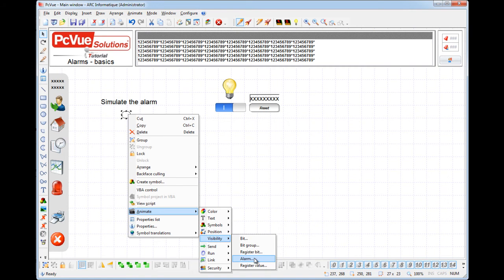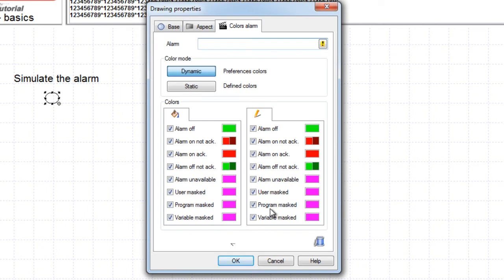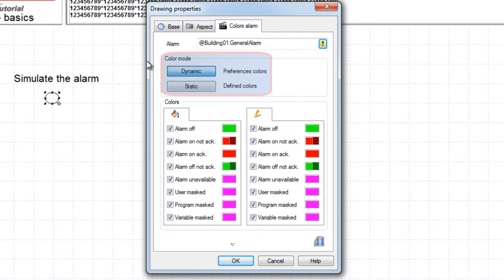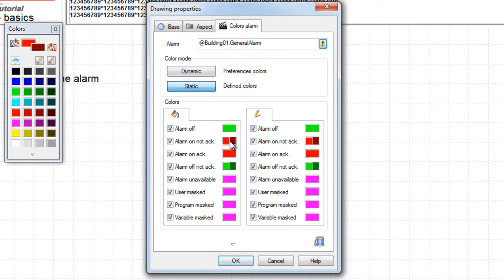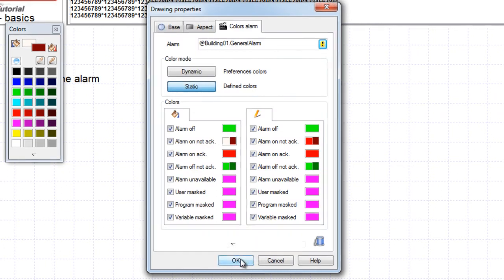Here we're going to use the color animation. The alarm animation displays the different states of a particular alarm, so select the alarm. You can choose a color for different states of the alarm, but by default the dynamic mode is selected. This means that the animation would use the project preference colors for alarms. Here we choose to define locally the colors for this particular animation using the static mode. Double-click on the color and select the color from the advanced color panel. Our button is now ready to go.